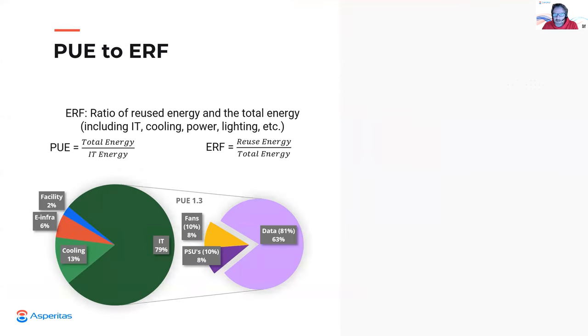You see, this is why PUE is now becoming a problem. After many years of good service, it's time to let go of this KPI as a dominating factor for the industry. Any energy which is spent on improving exergy will likely end up with a negative effect on PUE. Adding a heat pump to an existing free cooling installation, which is designed to simply throw out the hot air, will have a negative effect on PUE.